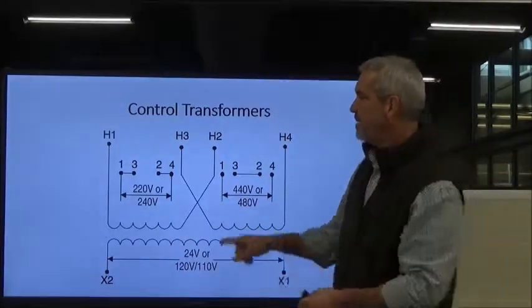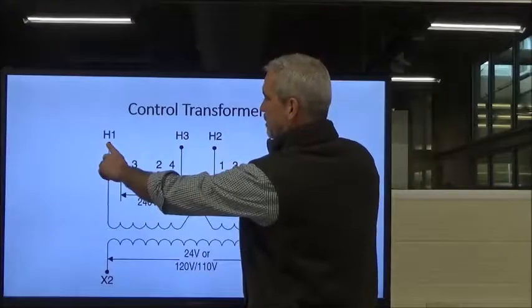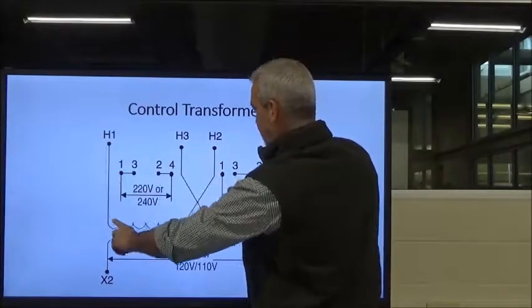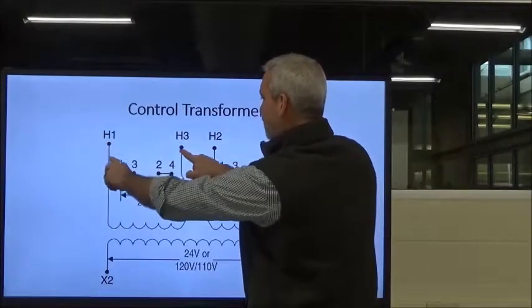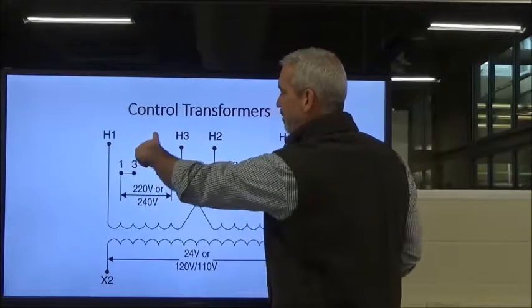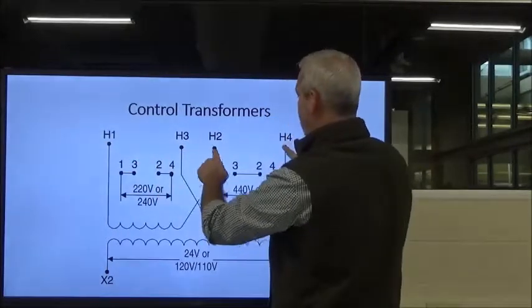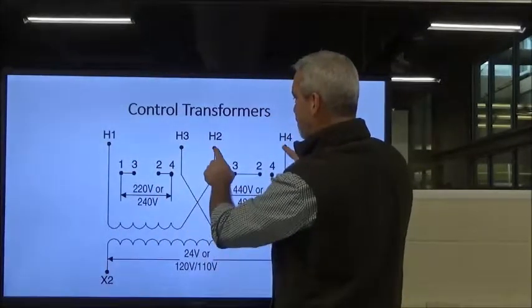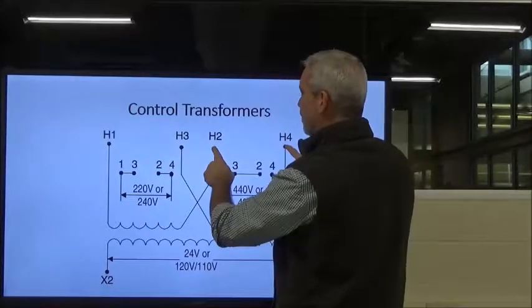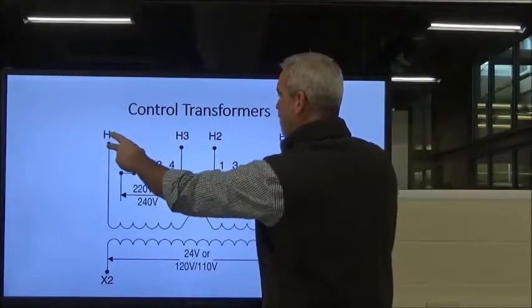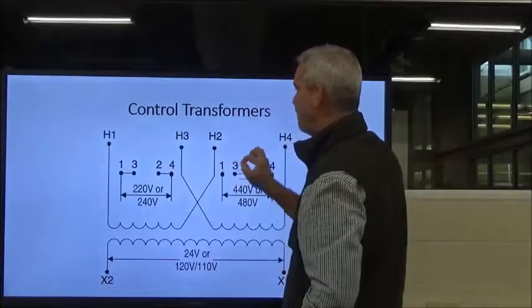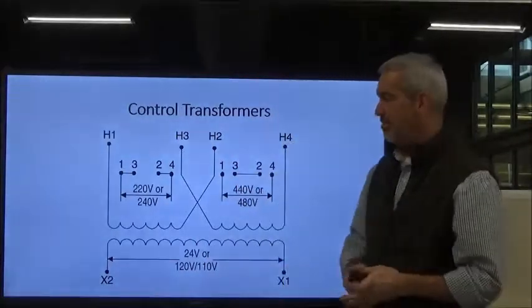So H1 and H3 - this is the incoming side of each coil, going to each side of the coil. H1 and H3 will be tied to one leg of our power. H2 and H4 is the outgoing side of this coil and the outgoing side of this coil. They're going to be tied together, so our power goes in here, and we have the other leg coming into H2 and 4. That puts them in parallel.